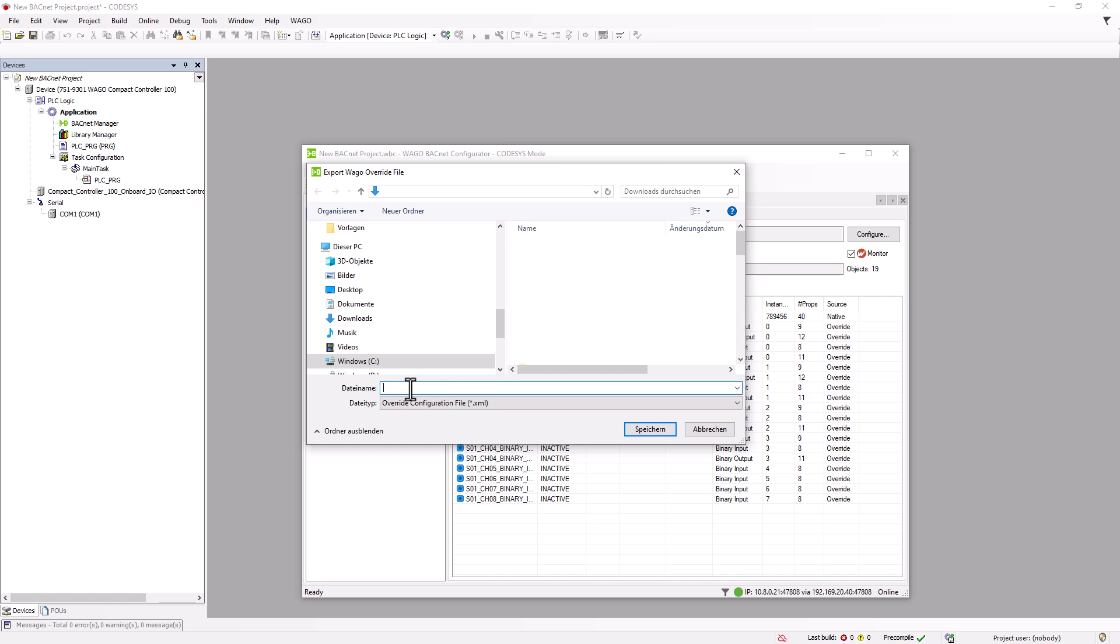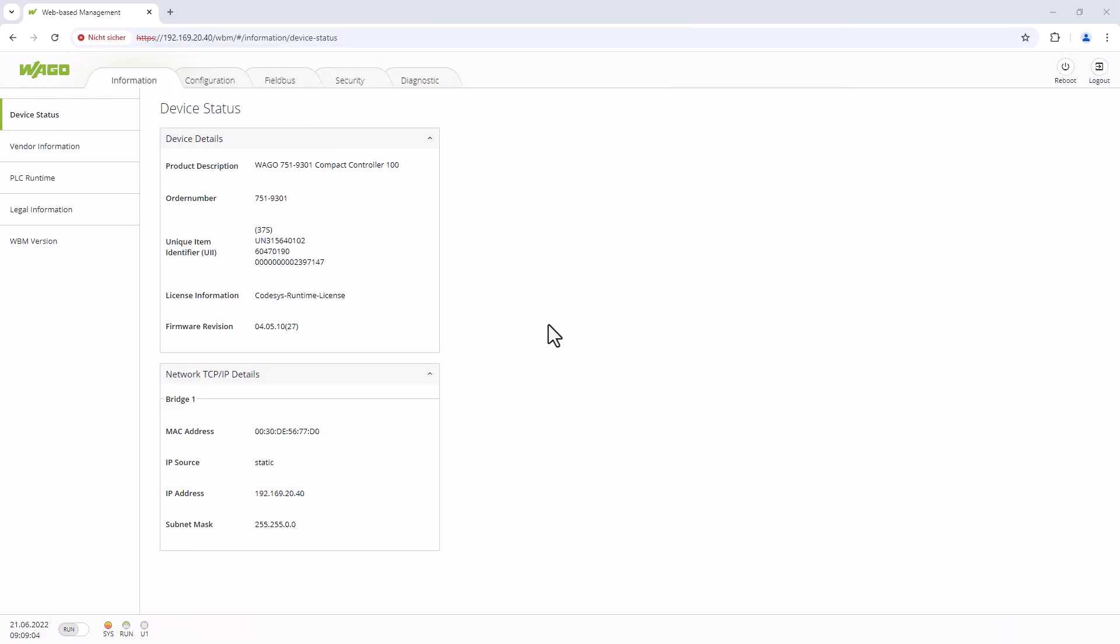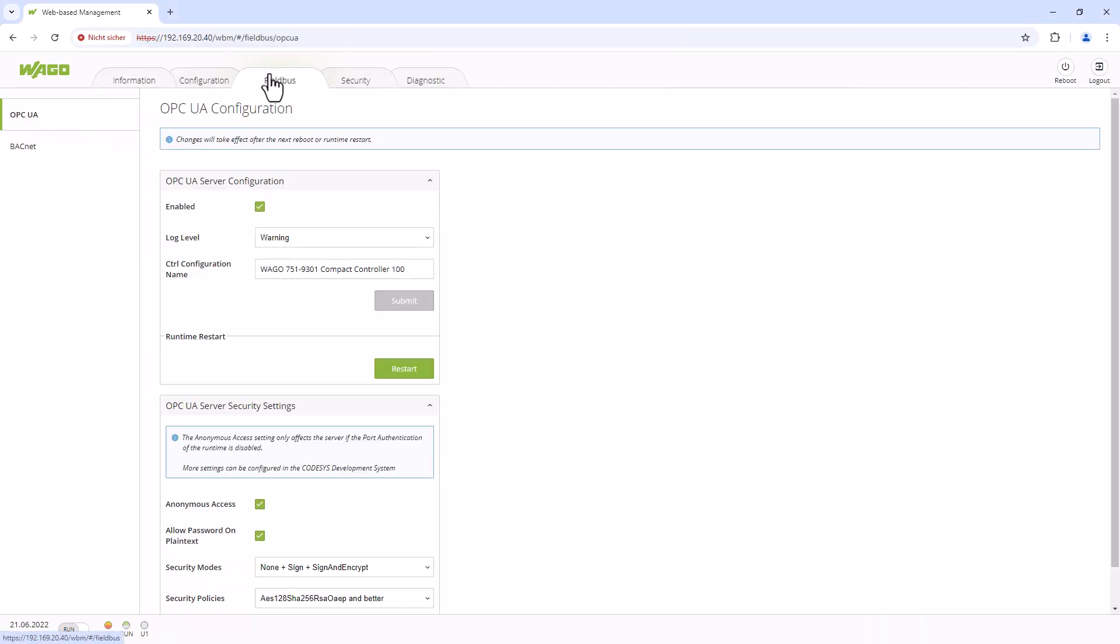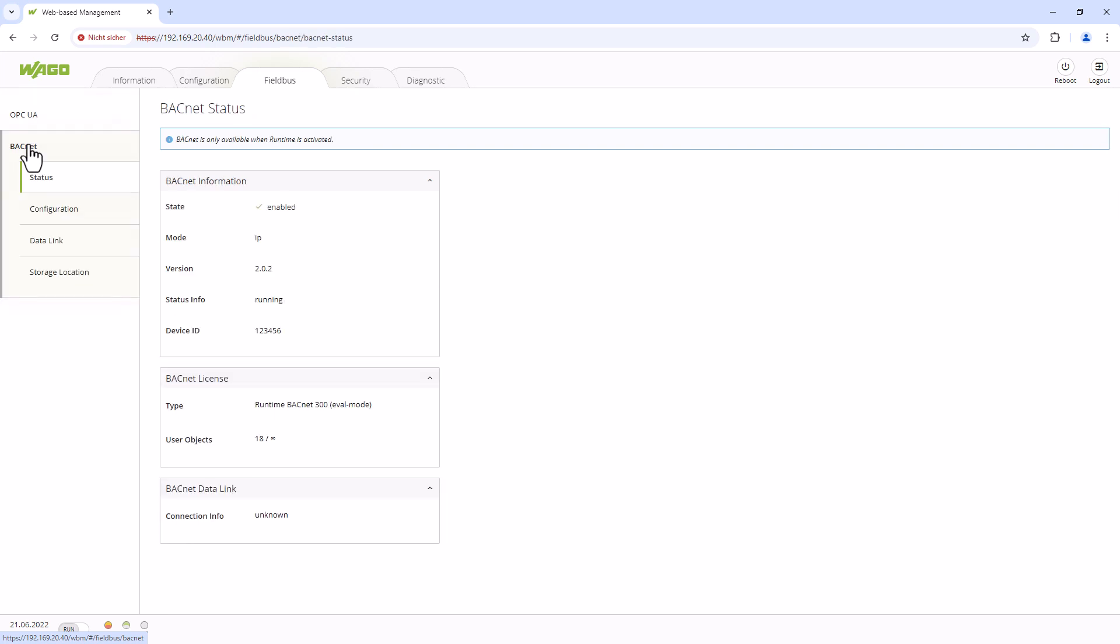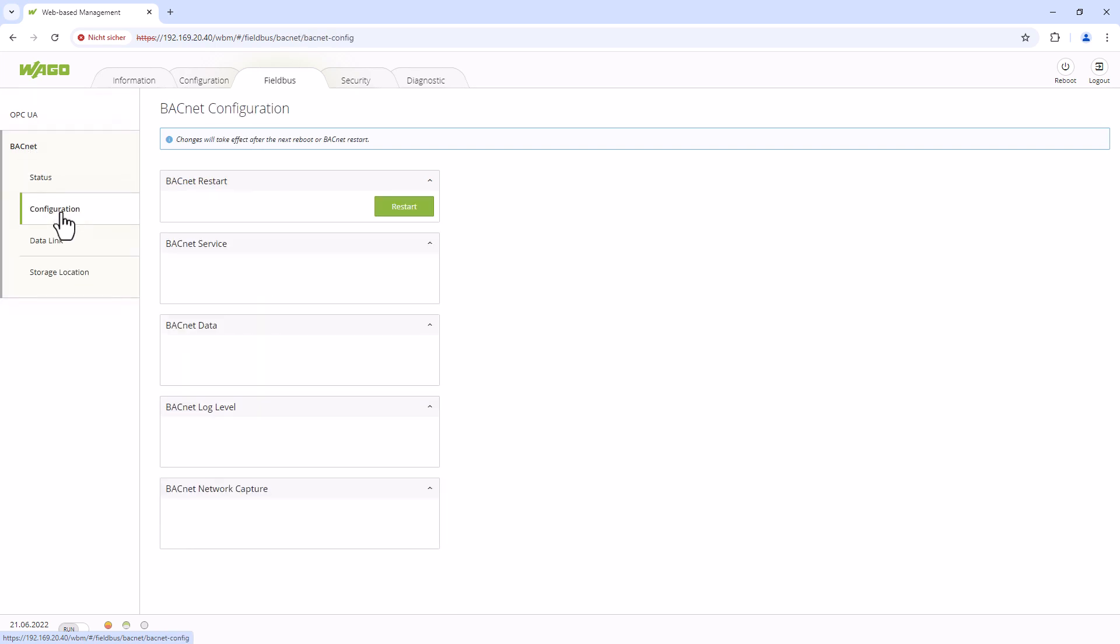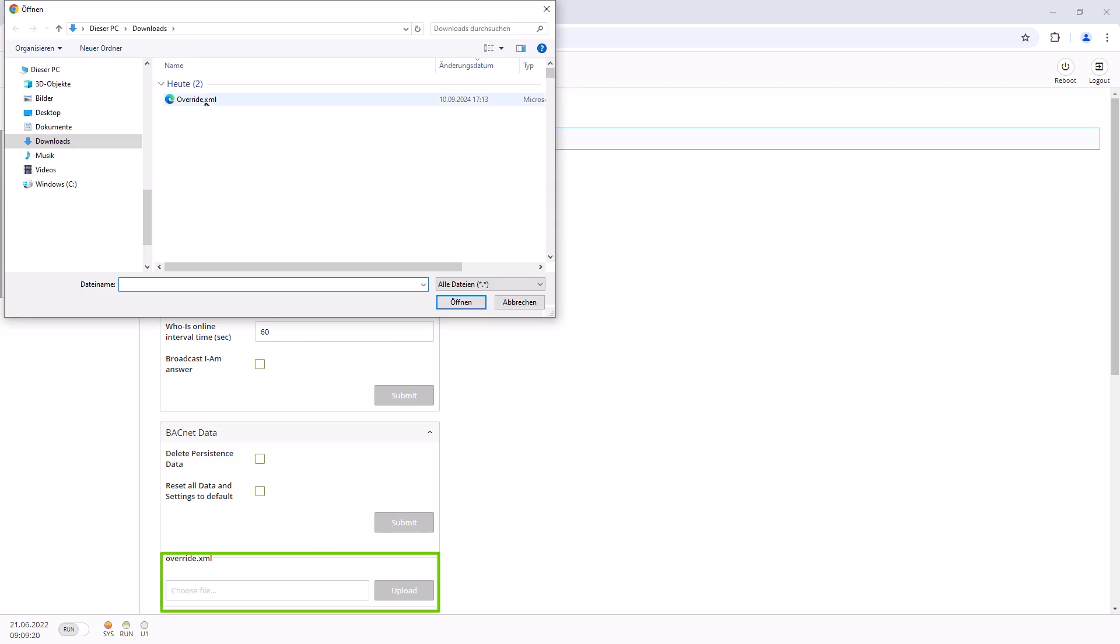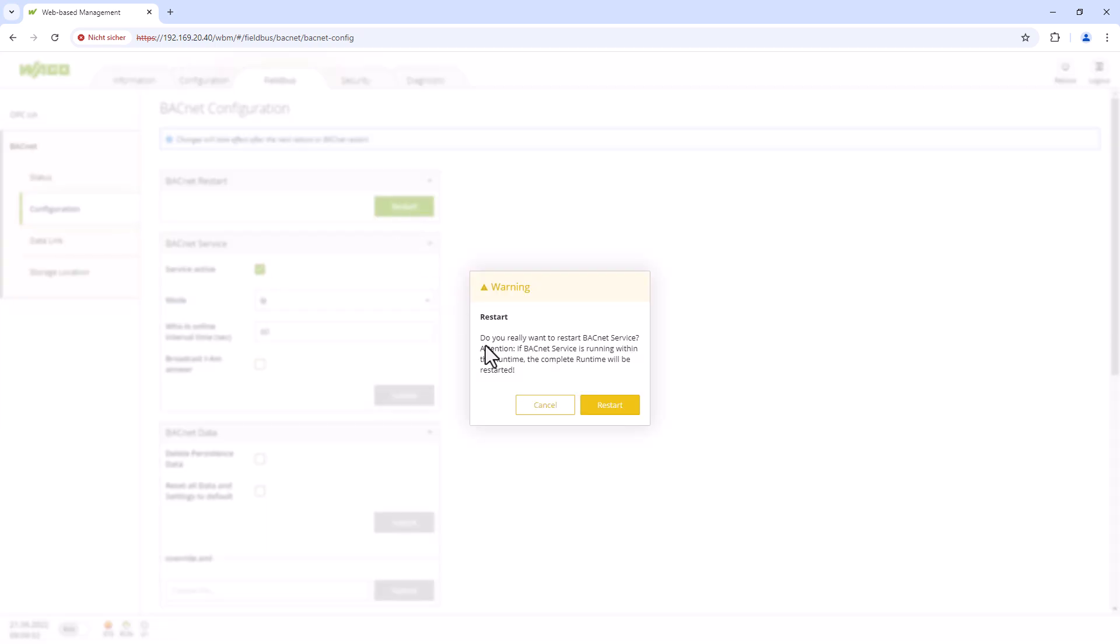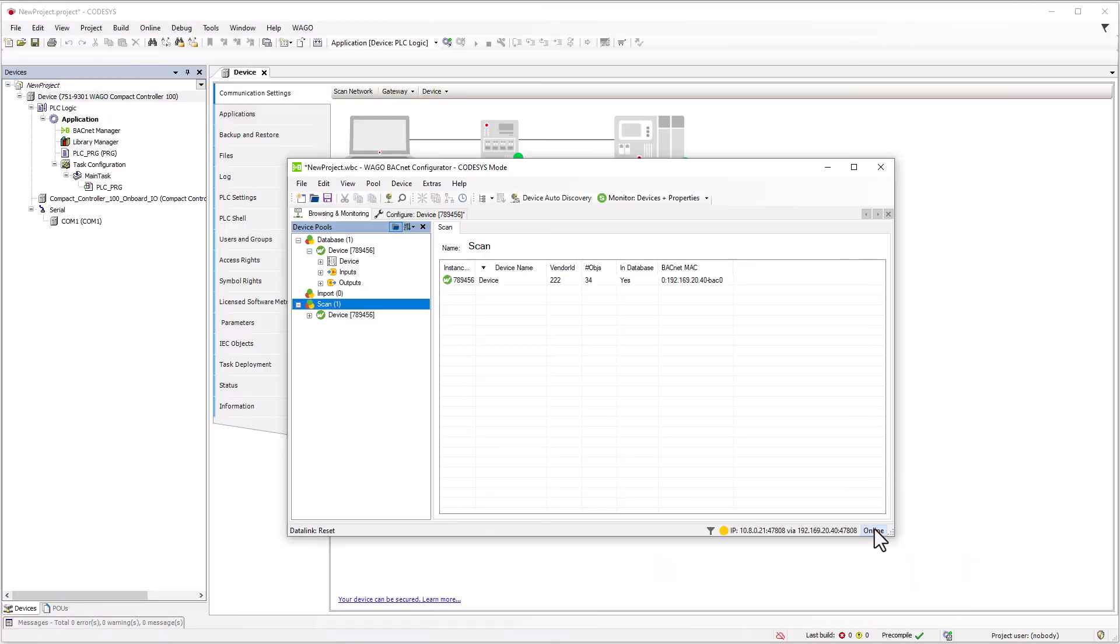Save the override file to your PC, then open the controller's web-based management. Go to Fieldbus, BACnet, Configuration and upload the override .xml file to the BACnet data area. Wait a moment for the upload to complete in the background. Restart the controller or just the runtime. And a connection as a foreign device is now possible.